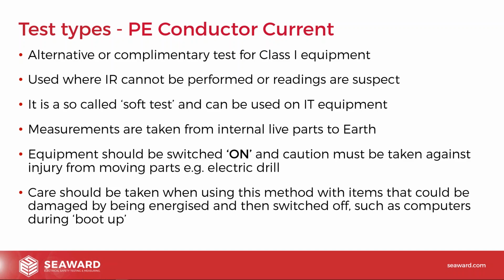And another thing to be aware of, just the final point mentioned on the slide, is to be careful if you are turning these things on for the period of time you set the test duration to. If you've got something like a computer and you set a 5-second test, it'll just start booting up, spin the hard disk up, and then you yank the power out. It can sometimes cause damage to things like hard disks. So just be careful when you are doing these. You might want to extend the time period for sensitive bits of equipment like that, to give you enough time to turn it on, boot it up, and shut it down again to actually measure. And you can generally adjust the test times in most of the testers.